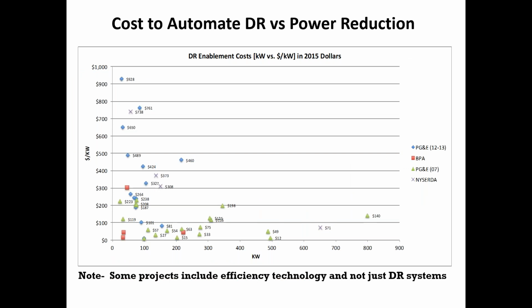This is a plot of the cost per kilowatt for installing the DR automation versus the number of kilowatts you get from a demand response event. You'll see PG&E as a blue diamond, a red square for Bonneville Power, a green triangle for PG&E in '07, and the X's are NYSERDA. There are different periods—some older PG&E data, some from 2012-2013. Most of the green triangles that are so low represent OpenADR 1.0.